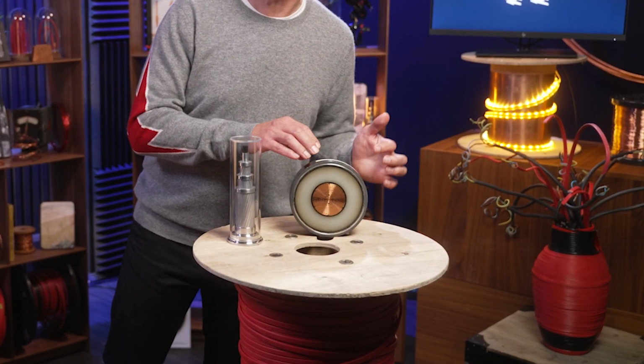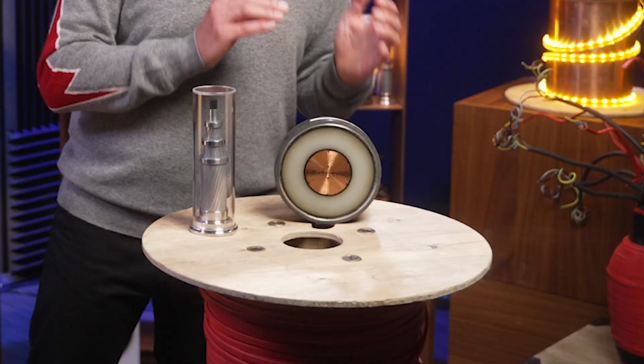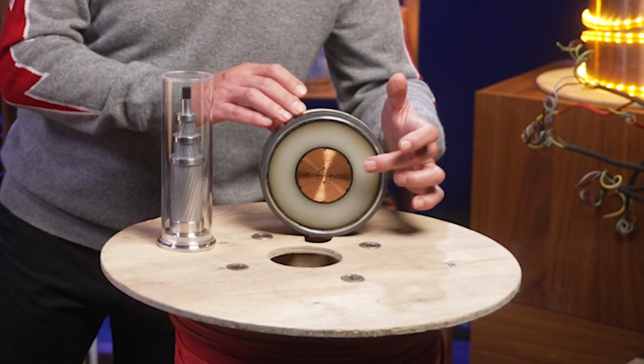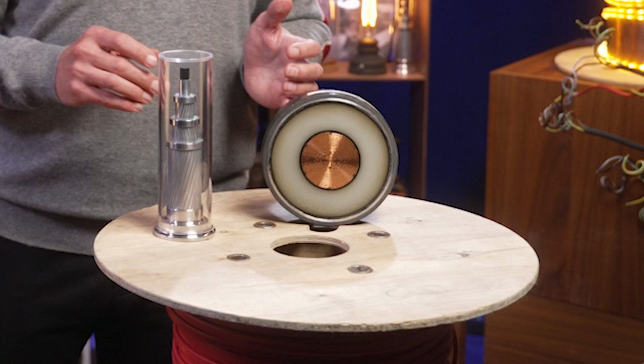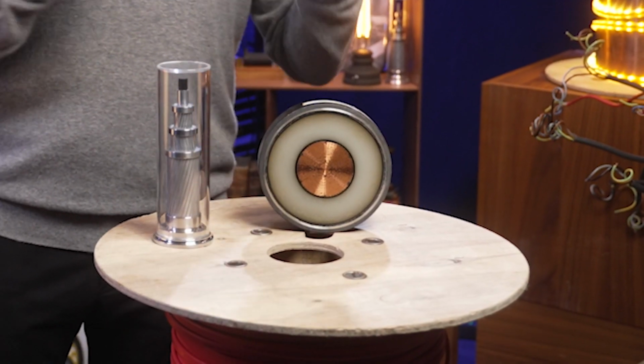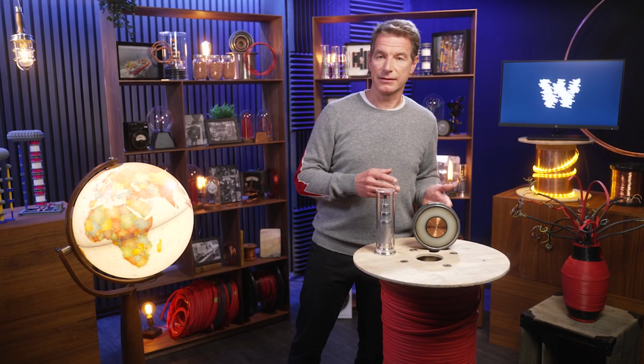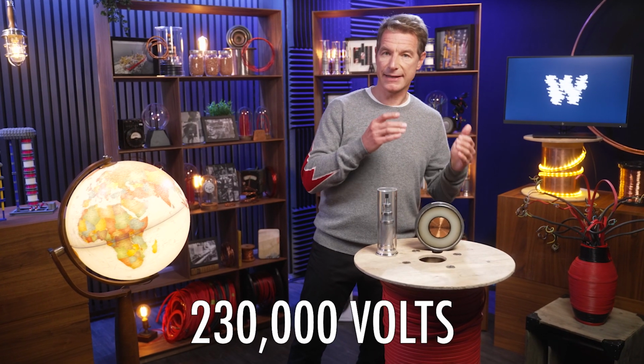In previous episodes we already described underground or submarine cables. The copper or aluminum conductor is insulated with polyethylene, a thick plastic layer that forms the insulation. The thicker it is, the higher the voltage it can withstand. This cable, for example, can withstand 230,000 volts, which is huge. But other extra high voltage cables can withstand twice that.